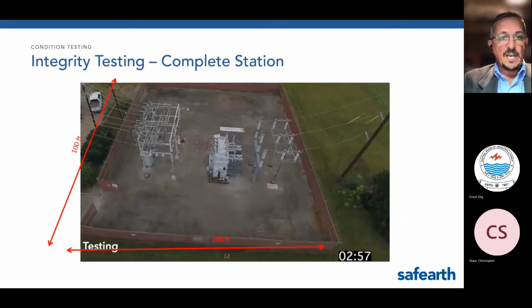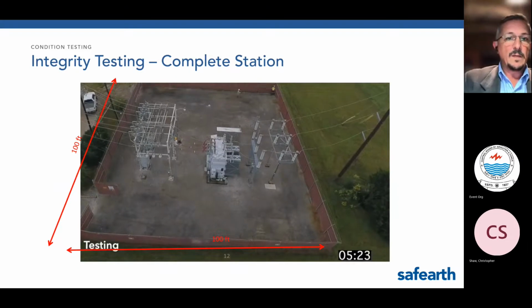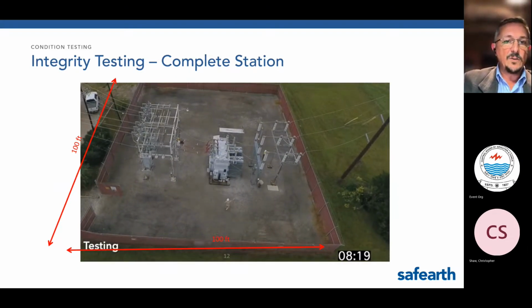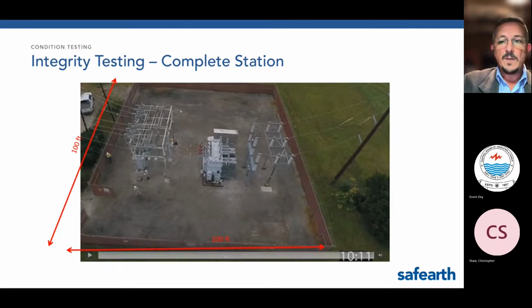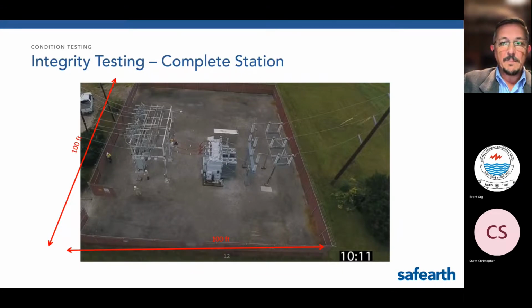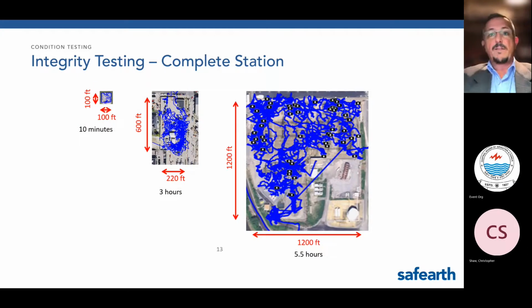Here's a highly sped up video of a continuity test underway. This is 10 minutes to test this yard, and it's not just testing every structure or every item, but it's taking multiple measurements to every one, so that even where there are multiple risers on, say, the transformer in the middle, you can check every one of those connections. Of course, many stations are much larger, but the speed allows even the largest site to be tested very thoroughly in a short period of time. The blue lines are actual track traces of staff who have been doing continuity tests throughout those 2 yards. And you can see that even a very large station is less than a day.